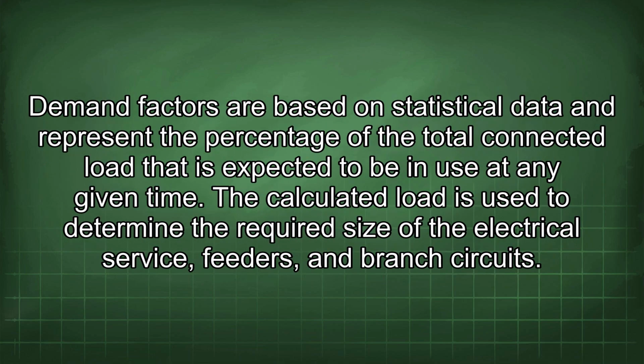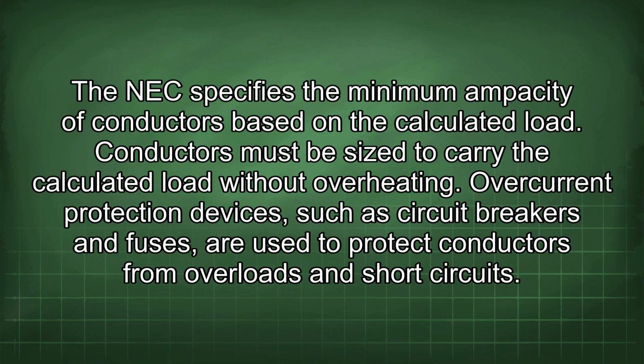Demand factors are based on statistical data and represent the percentage of the total connected load that is expected to be in use at any given time. The calculated load is used to determine the required size of the electrical service, feeders, and branch circuits. The NEC specifies the minimum ampacity of conductors based on the calculated load. Conductors must be sized to carry the calculated load without overheating.